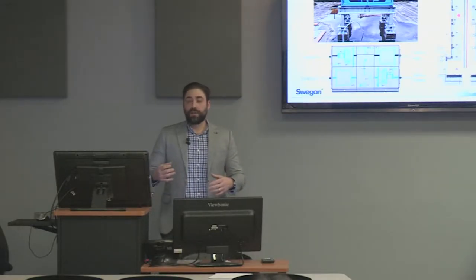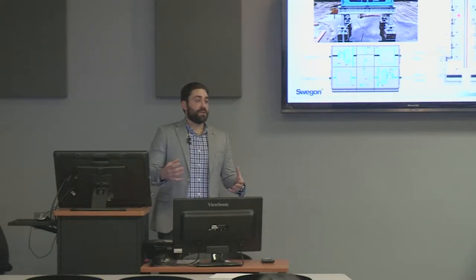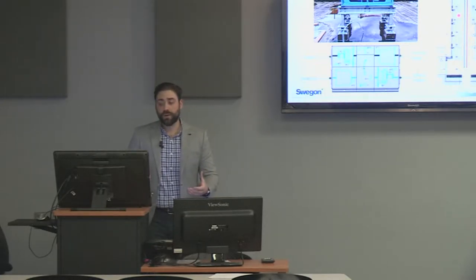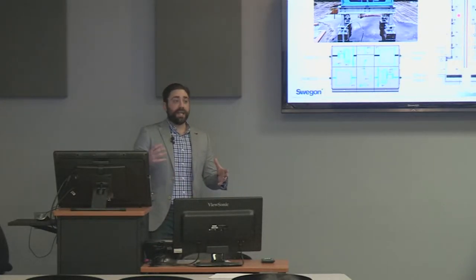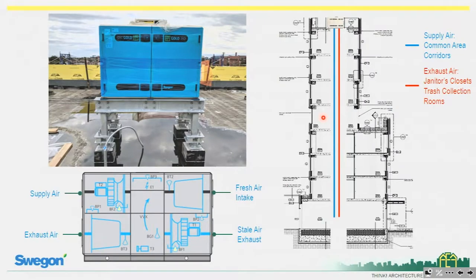For the corridors and all the common area spaces, we're using a centralized system — specifically the Swegon RX Gold. This product is actually an HRV, so it's just heat recovery. We're finding through research and seeing more of these buildings built around the country that it may be beneficial to not recover moisture in common area spaces where we have a lot of excess moisture being produced. During the wintertime, we may choose not to recover that, so we're going with the HRV option in this case.